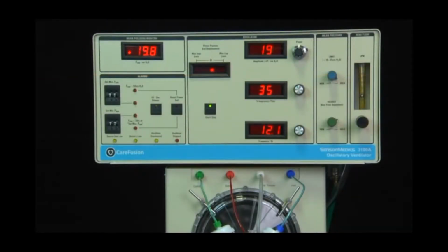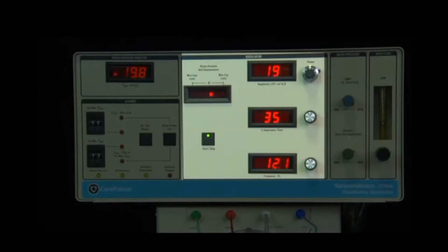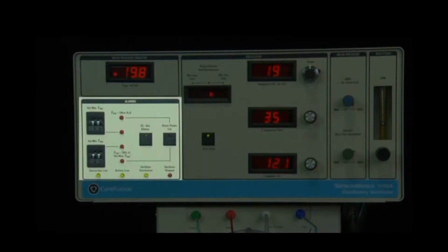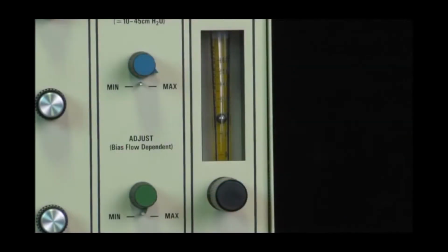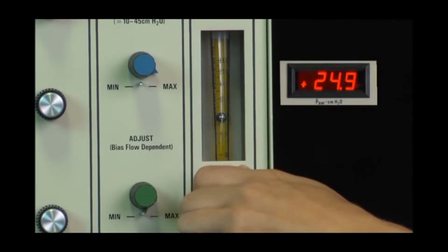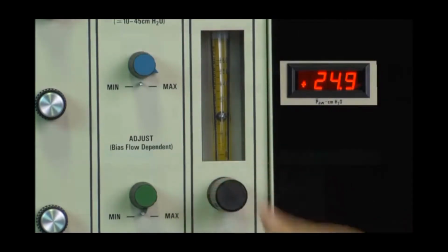The front panel can be divided into 3 sections: controls and displays for mean airway pressure, high-frequency oscillation, and alarm package. This sets the continuous gas flow through the system and is used to establish the mean airway pressure. Although the ventilator has a maximum flow rate of 40 liters per minute, typical applications use flow rates of only 10 to 15 liters per minute for newborns and 15 to 30 liters per minute for children. Since the mean airway pressure is flow dependent, adjustments to the flow rate will affect the mean airway pressure range.